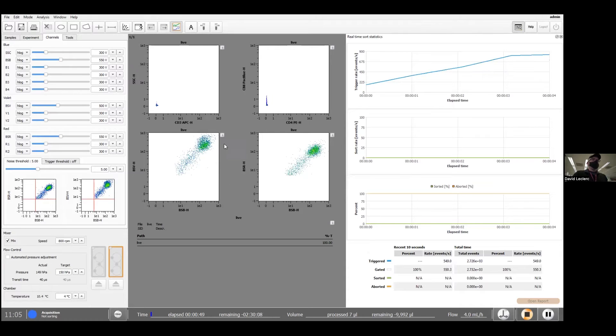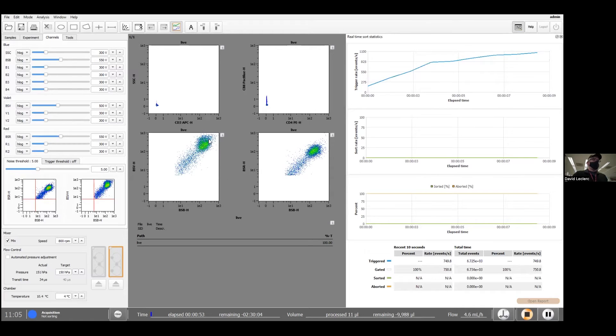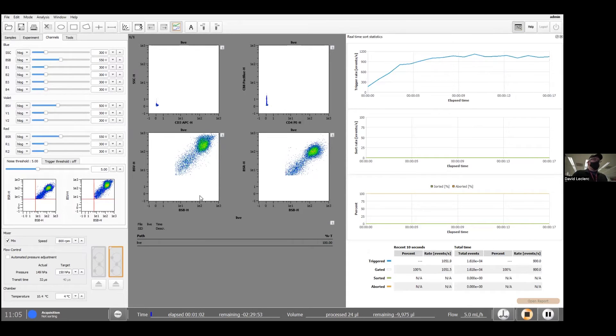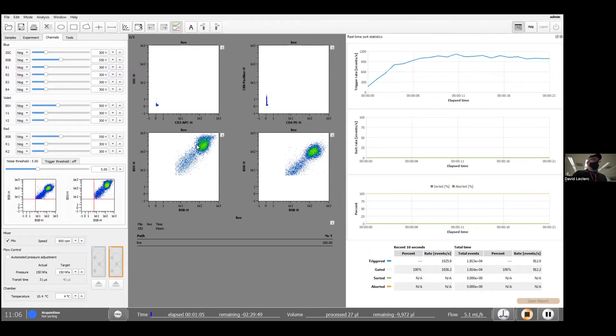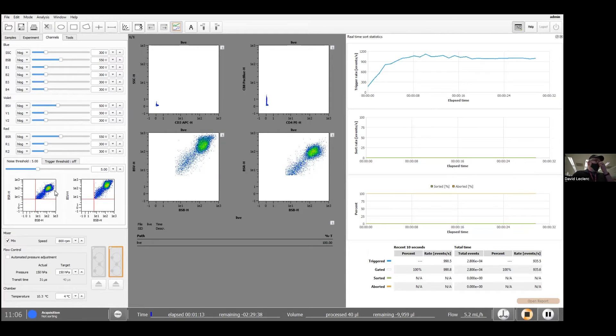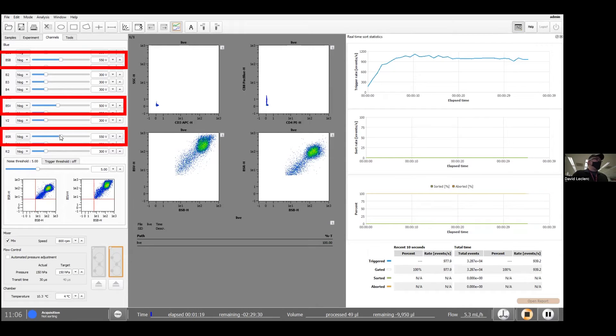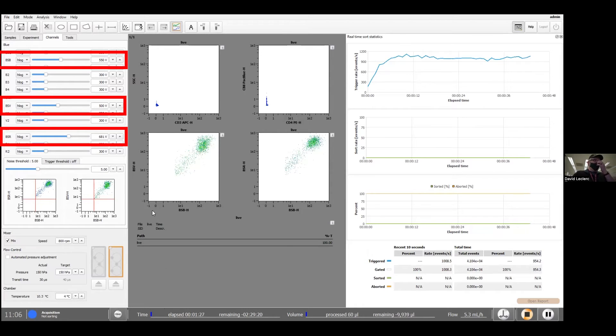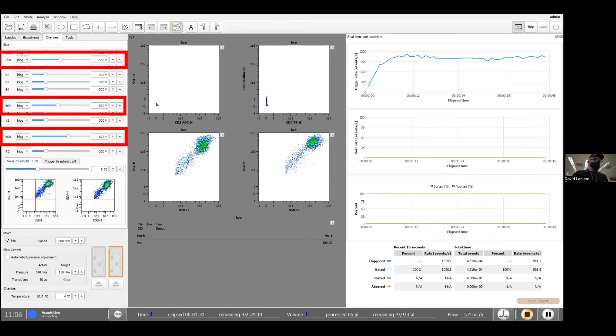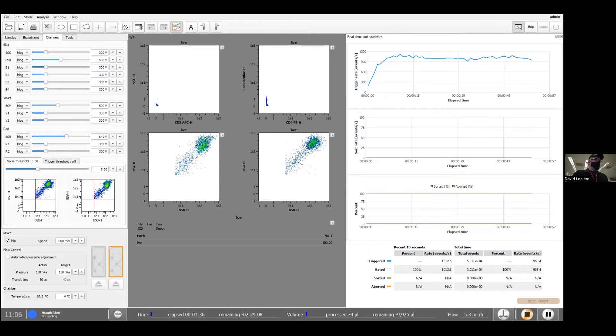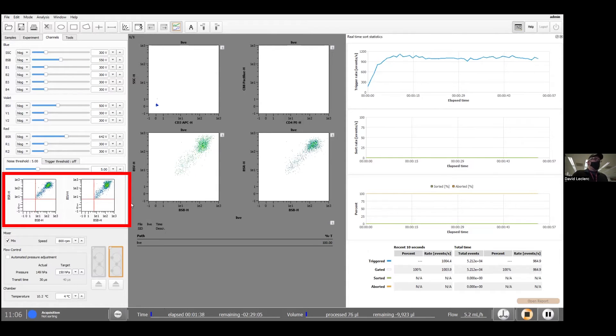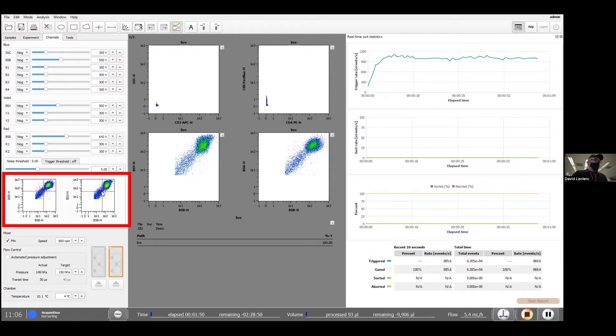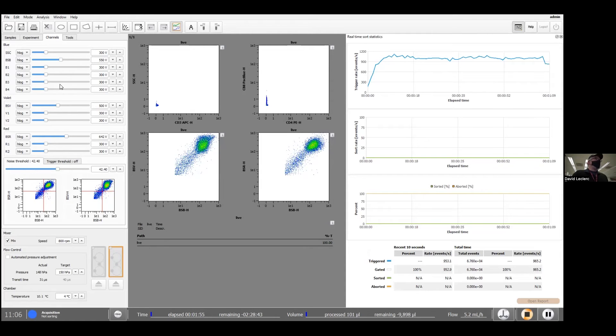So the data started showing up on our graph. And so what I typically do is set the voltage for my backscatter detectors for all three lasers. Essentially what we're trying to do is get them as high as possible on the axis without saturating the detector. And all of them should have about the same intensity. So I have the same two graphs over here as I have under my threshold. So I'm simply going to increase the backscatter red voltage. Whenever I do that, I have a clear button that allows me to refresh. That's a bit too high, but we're getting there. Once I'm happy with the values I get, then I can set my threshold to essentially anything that's not part of the cluster of cells I'm interested in.